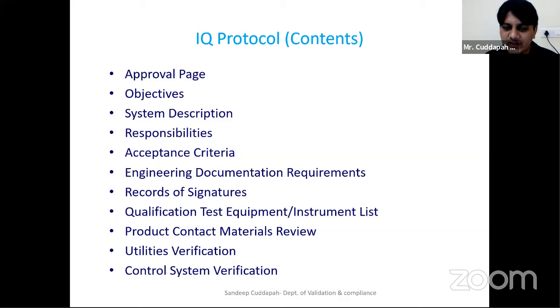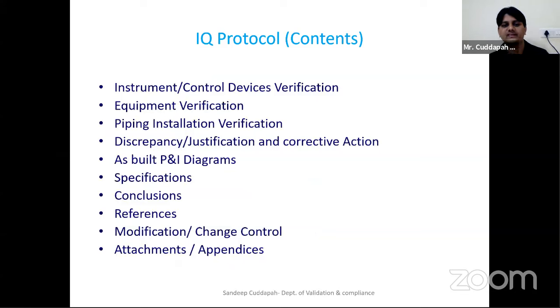Then you have the qualification test equipment or instrumentation list. As I told you, if you want to qualify any equipment, a sub equipment or your measuring instrument, that list of measuring instruments should be given in the installation qualification. Then utility verification. For some bigger equipment, you have to connect many utilities, like power, water, and steam. So many kinds of utilities come into the picture, and you verify those utilities in the installation qualification. Then the control systems you have will also be verified during installation qualification.